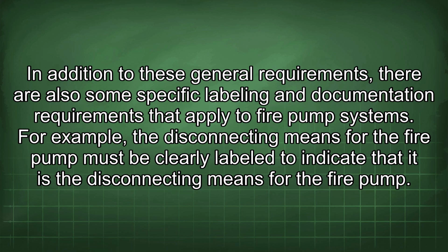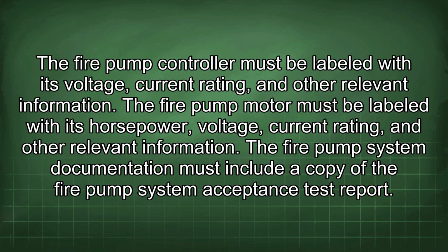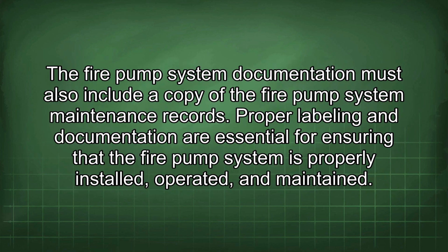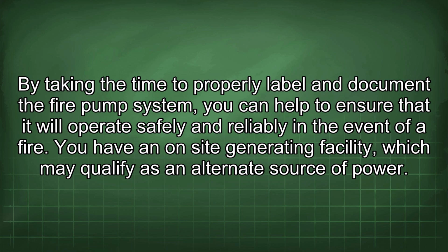In addition to these general requirements, there are also some specific labeling and documentation requirements that apply to fire pump systems. For example, the disconnecting means for the fire pump must be clearly labeled to indicate that it is the disconnecting means for the fire pump. The fire pump controller must be labeled with its voltage, current rating, and other relevant information. The fire pump motor must be labeled with its horsepower, voltage, current rating, and other relevant information. The fire pump system documentation must include a copy of the fire pump system acceptance test report. The fire pump system documentation must also include a copy of the fire pump system maintenance records. Proper labeling and documentation are essential for ensuring that the fire pump system is properly installed, operated, and maintained. By taking the time to properly label and document the fire pump system, you can help to ensure that it will operate safely and reliably in the event of a fire.